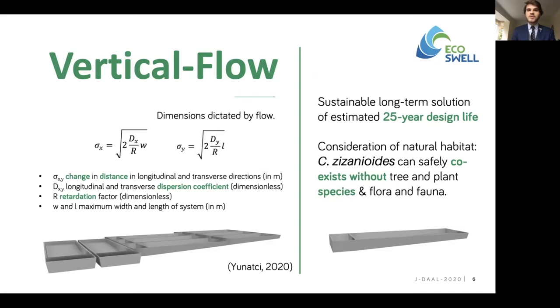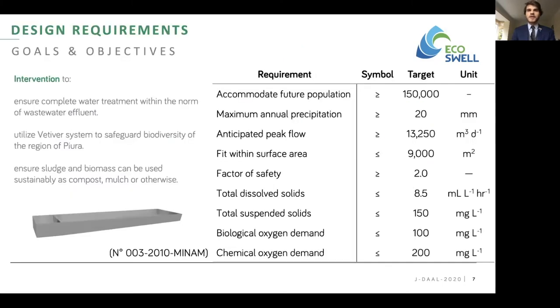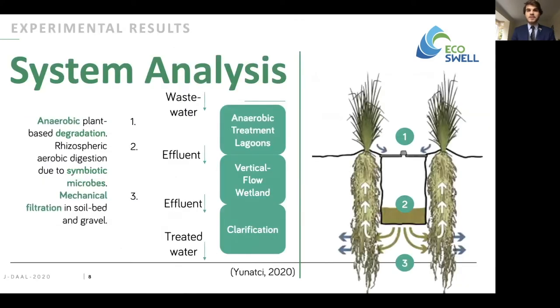The system was designed for an estimated 25-year design life, based on 2% annual compounded growth, amounting to approximately 150,000 residents by 2045. Final design requirements were to support a peak flow of 13,000 m³/day, informed by maximum precipitation of 20 mm per annum. The design must also consider extreme flooding events, for example during an El Niño Southern Oscillation. The intervention fits within approximately two and a half acres, supports treatment to national wastewater effluent quality standards, and must safeguard native biodiversity while allowing sludge and biomass generated to be reused. The substrate properties were determined by the type of retention required to reduce BOD, COD, and thermotolerant coliforms to within national standards.